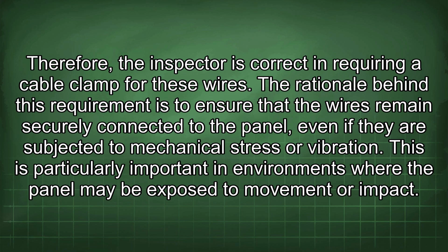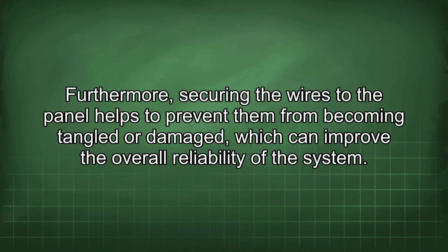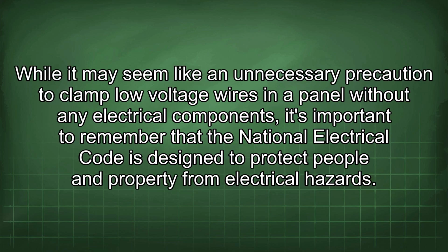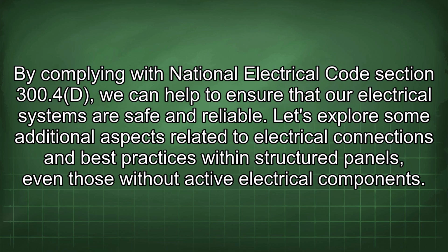This is particularly important in environments where the panel may be exposed to movement or impact. Furthermore, securing the wires to the panel helps to prevent them from becoming tangled or damaged, which can improve the overall reliability of the system. While it may seem like an unnecessary precaution to clamp low voltage wires in a panel without any electrical components, it's important to remember that the National Electrical Code is designed to protect people and property from electrical hazards. By complying with National Electrical Code Section 300.4(D), we can help to ensure that our electrical systems are safe and reliable.